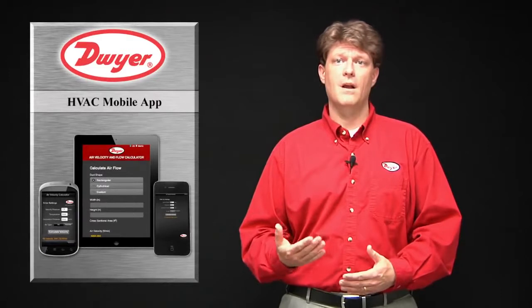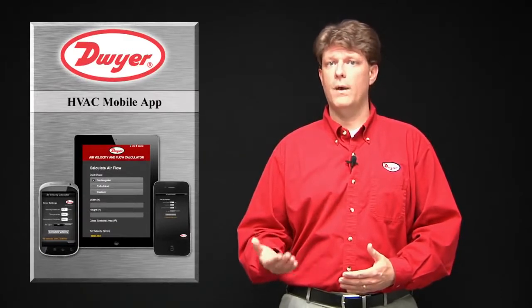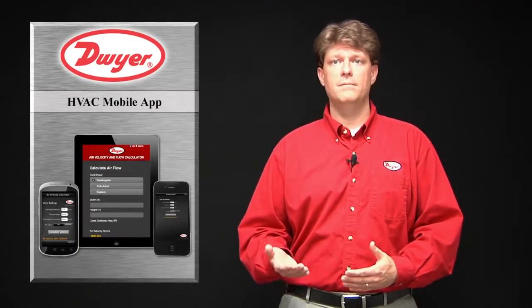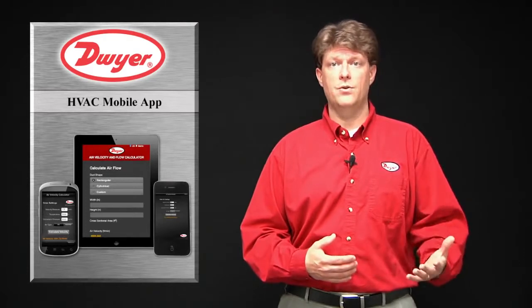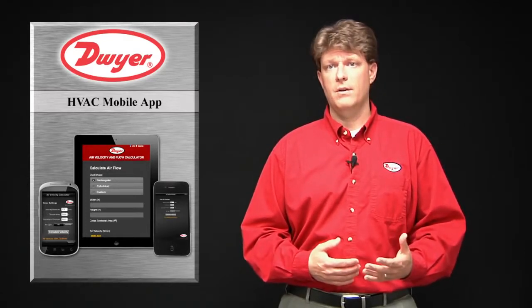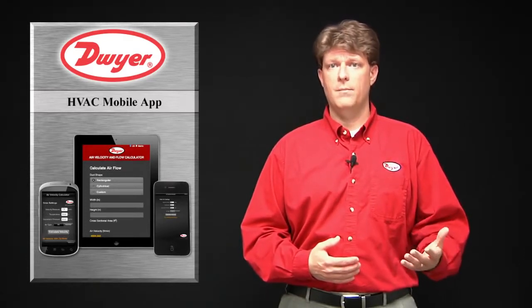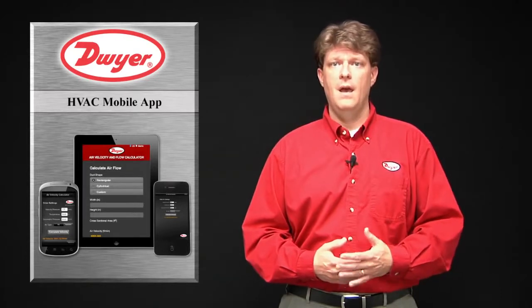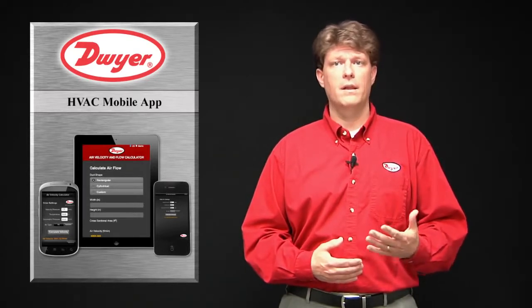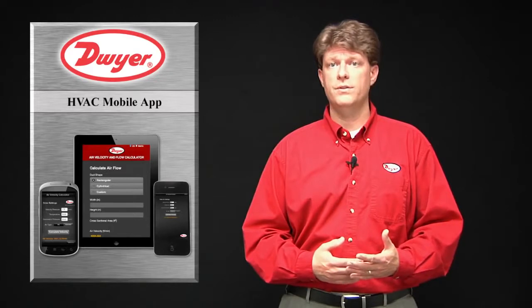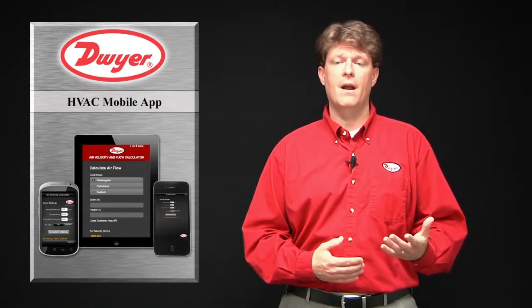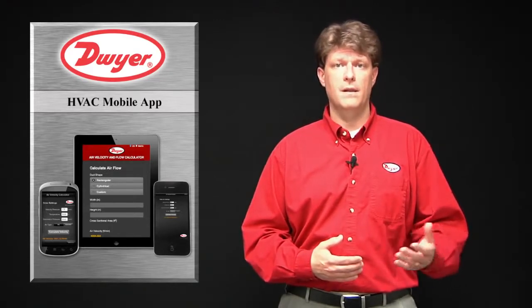Dwyer also has an air velocity and flow calculator on our website and downloadable as a mobile application for Apple and Android devices. This calculator will take the velocity pressure and calculate velocity, and with cross-sectional area will calculate air volume flow rate. It also offers the ability to make air density corrections for humidity levels.